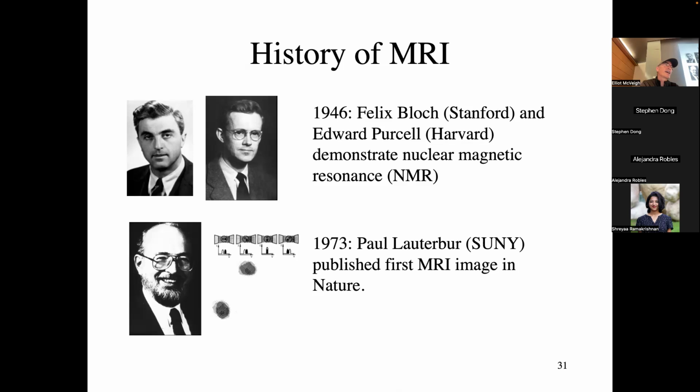And in order to do that, they gave you a set of dials and a set of coils that took the magnetic field and changed it as a function of position in space slightly to compensate for problems with the main magnetic field. So you could set these dials and then get a perfectly flat, beautifully constant magnetic field over your whole sample. And then you get essentially the spectrum of all of the NMR that's going on in that sample.